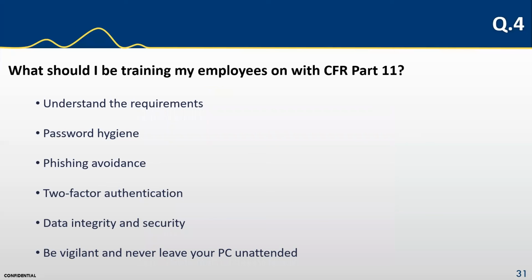Question 4, what should I be training my employees on with 21 CFR Part 11? Well, obviously understanding the requirements, password hygiene, avoiding any phishing attempts. There's a lot of that going on out there, folks. A lot of hackers. Definitely have two-factor authentication, data integrity and security, and be vigilant and never leave your PC unattended. And also make sure that the systems you're using have timeouts. So if you go away from your particle counter or your real-time monitoring system, it will time out after X amount of minutes as well.